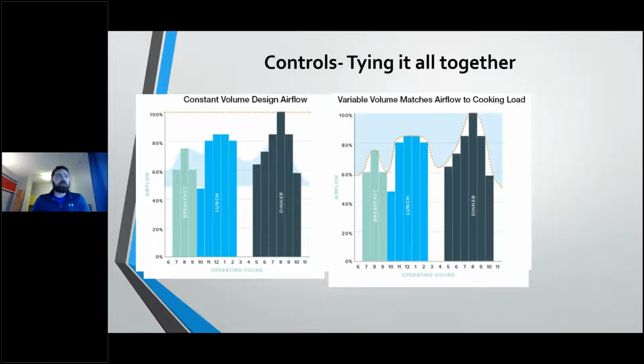That is important to remember for the variable volume system. So even if this thing is operating at 50%, if somebody goes and pulls that manual pull station, code requires that that fan operate at 100% of design. And again, these control packages are going to have all of that interlocked within them.